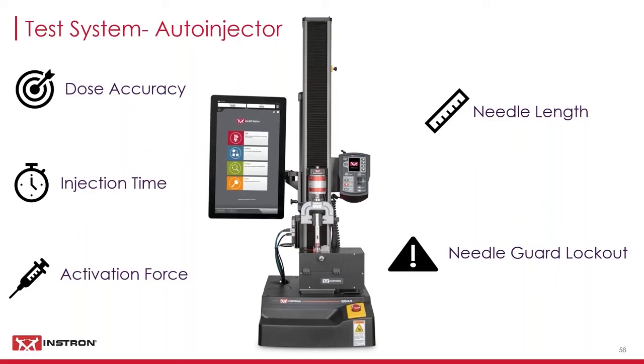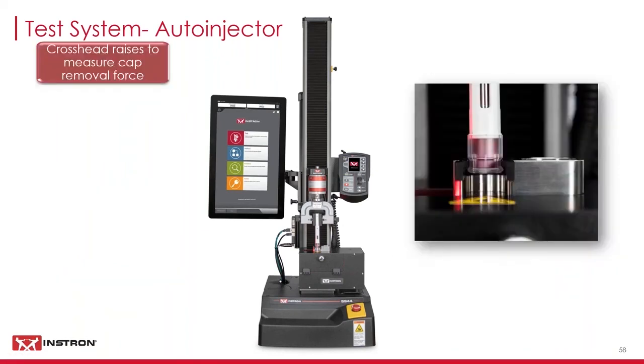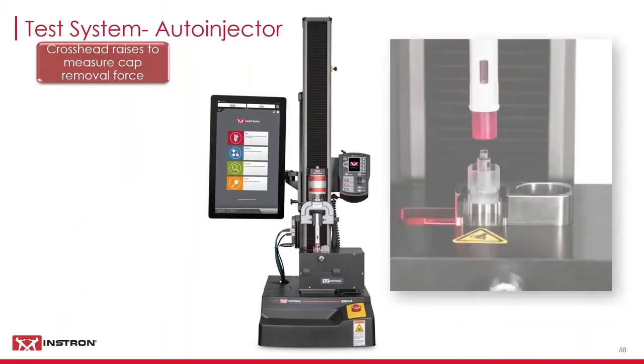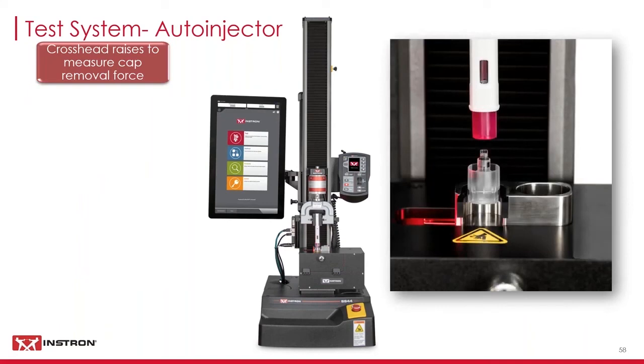This system shows an auto-injector test stand running with Blue Hill Universal. The operator places the device into the cap insert and secures in the grips. Then they press start to begin the test. First, the crosshead moves up to remove the cap and records the maximum force.